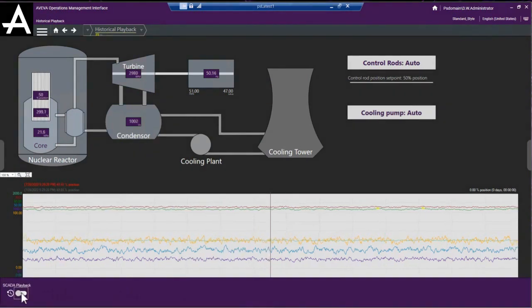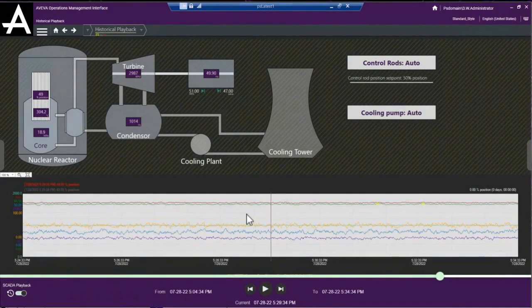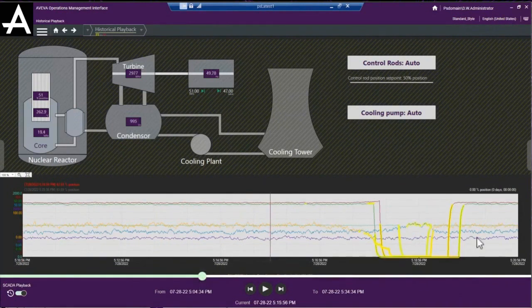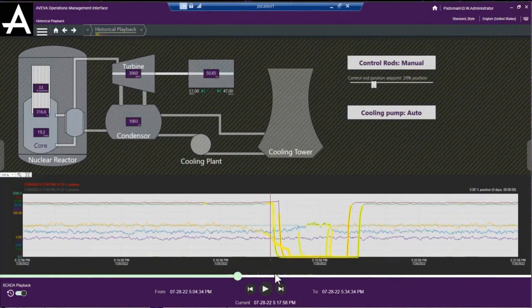So what you're looking there, of course, is a live system. I put it into playback. I put some chevrons on there to show it's in live playback mode. I also linked the trend control just for fun, so as you slide the slider along and put yourself at a different date, the trend control slider is attached to that. It's pretty easy to do that. So I can say, I've got some alarm sitting there, and I can put myself into playback mode to go and play through all of these alarm conditions in real time. So it's basically playing back history.